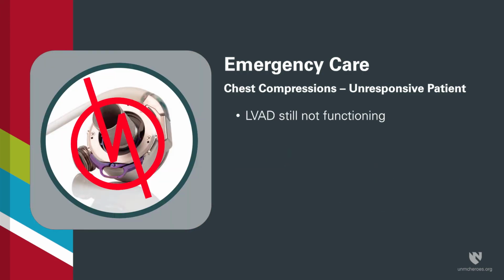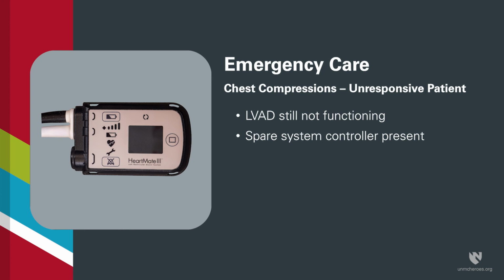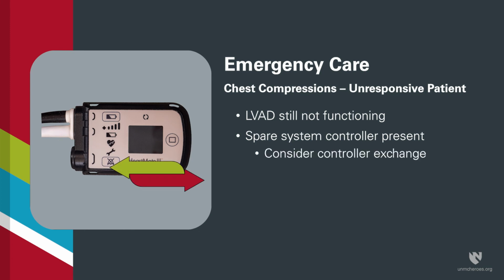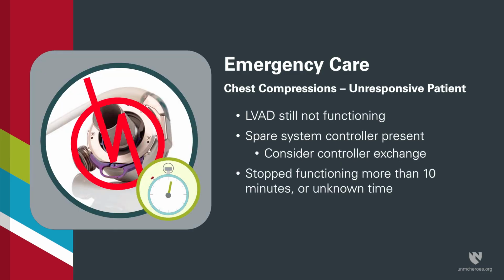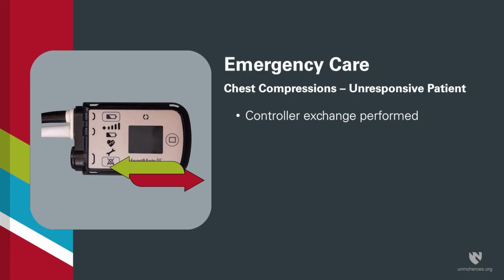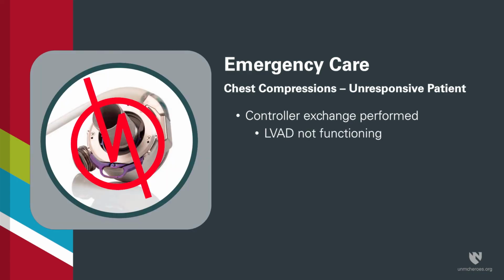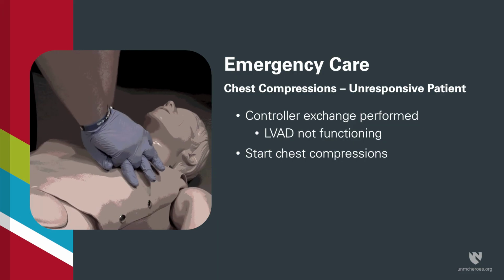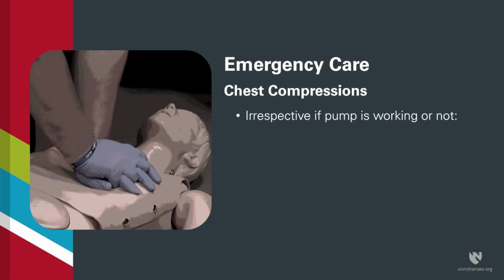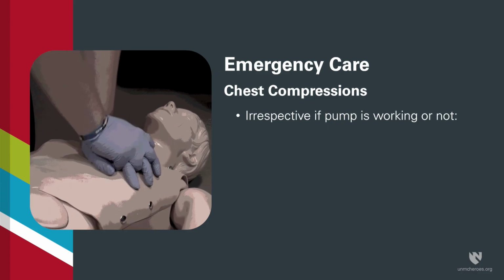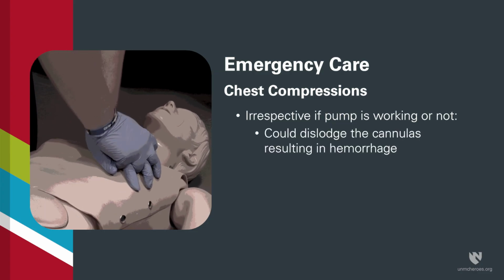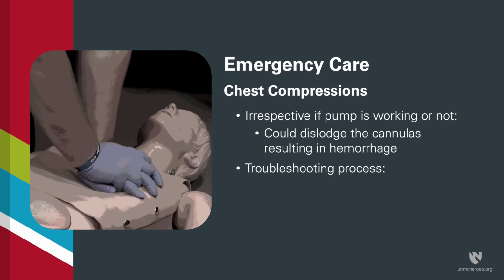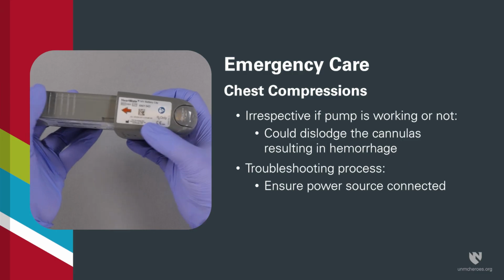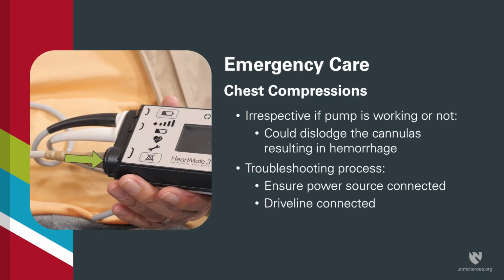If the LVAD is still not functioning and a spare system controller is present, the responder can consider a controller exchange. However, if the LVAD has stopped functioning for more than 10 minutes or the time is unknown, do not attempt to exchange the controller. If the controller exchange is performed and the LVAD is still not functioning after the exchange, chest compressions should be started. Starting chest compressions, irrespective of whether a pump is functioning properly or not, could dislodge the cannulas, resulting in hemorrhage. As part of the troubleshooting process, ensure the power source is connected and the driveline is connected.